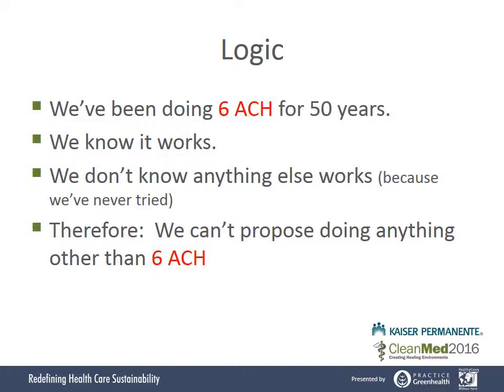Now, the funny thing is - at least I think it's funny, that guy wouldn't - the committee changed patient rooms from 6 air changes per hour to 4 air changes per hour like 6 months later. They didn't do any research, they just changed it. In California where I live, our code actually says you can do 2 air changes per hour. They didn't do any research behind that either. They just have it different.